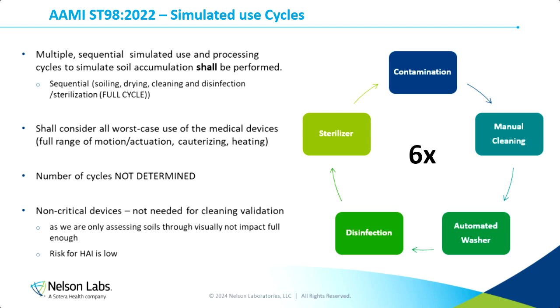One thing is that the number of these simulated use cycles is not determined in ST98, so it's not a set requirement of how many you need. But we typically recommend 6, which is the industry standard that's been around for a little while. For non-critical devices, these simulated use cycles are not needed prior to the cleaning validation. Most of the time, which I'll get into further in the presentation, non-critical devices at minimum just need to be visually clean as part of the criteria for their cleaning validation. There's not much risk associated with accumulation of soil over time, hence these cycles are not typically required for these devices.